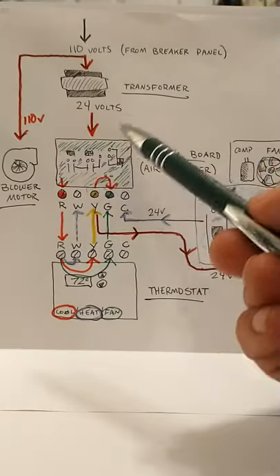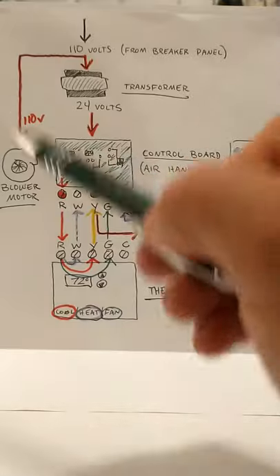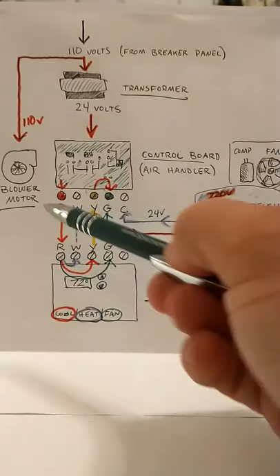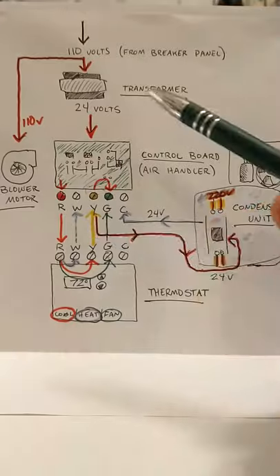And basically, you could just leave that jumper in there. It doesn't matter. That jumper just turns it into one single R terminal. And you still run your heating off your W and your Y.